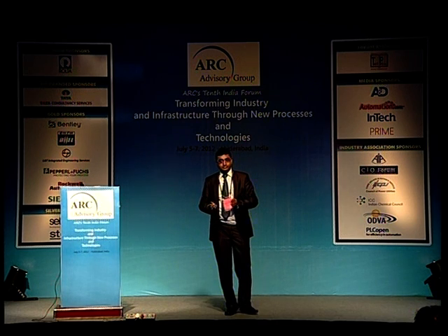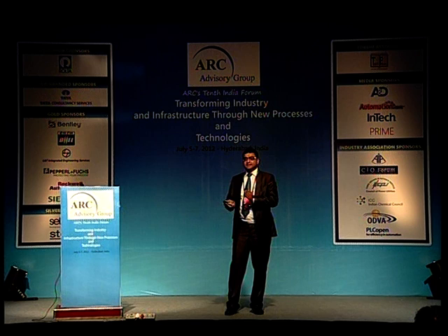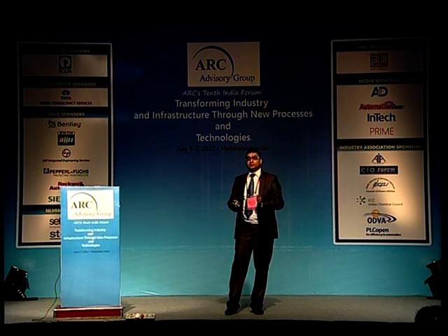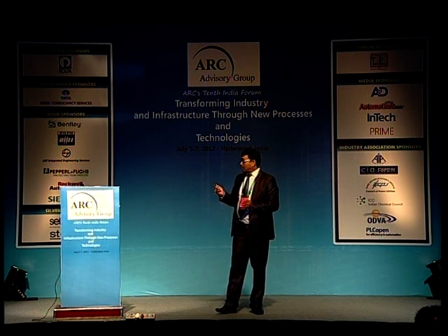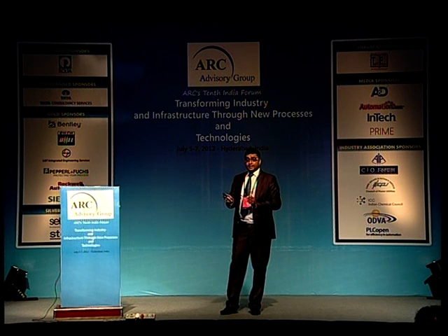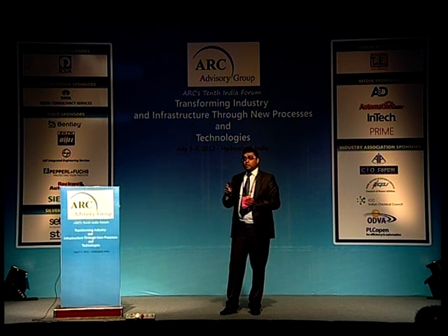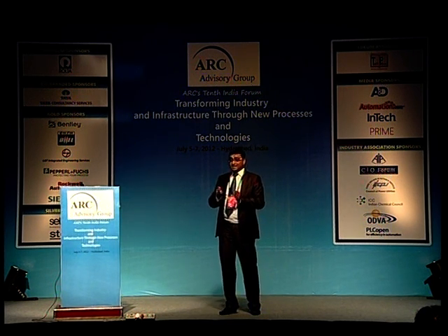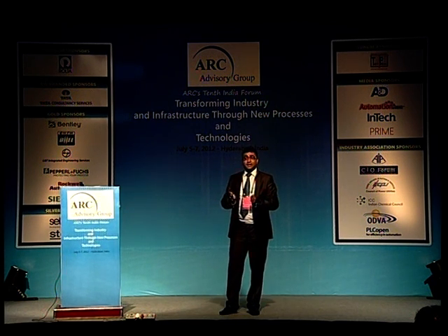What does it mean? Best achievable means, if it is designed, then of course there may be a big gap between existing performance and the best achievable performance. Our Pardo performance monitoring system calculates online, from a thermodynamic based model, the best achievable based on the current cold end and the current ambient conditions. Whatever you can achieve in the current scenario is what is given as the best achievable. That helps the operator see where the deviation is happening and where he is losing money.